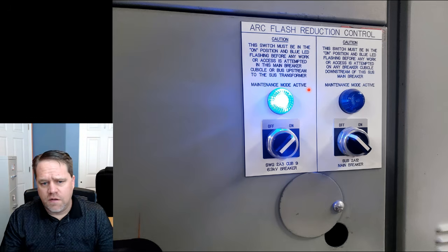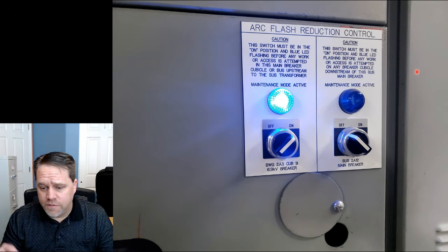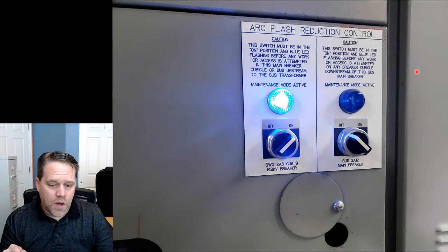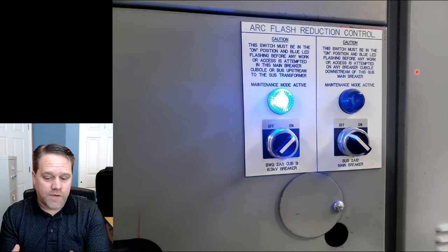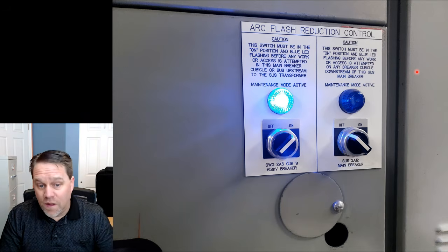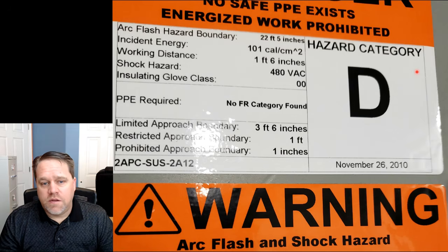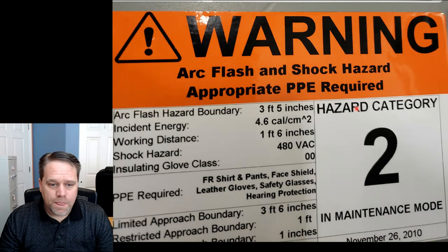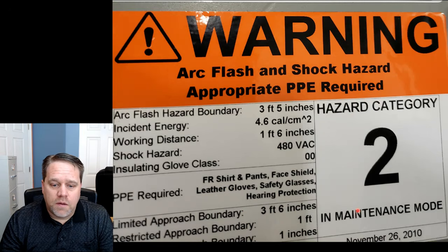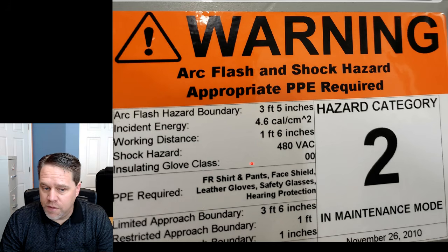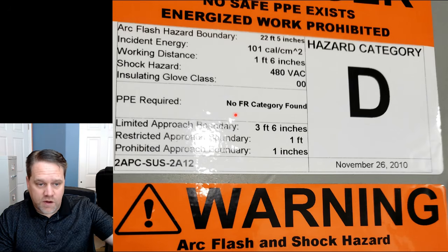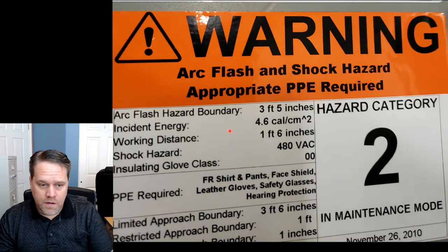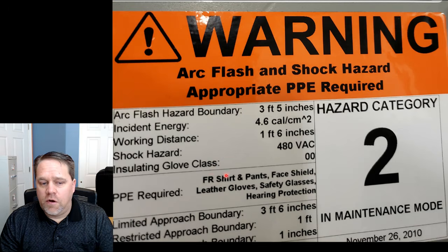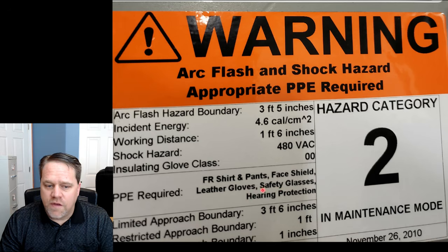What they have here is a relay, and then they also have optical fiber that actually is looking inside the equipment, and if they see a flash through the optical fiber line, it opens in less than one cycle. So it takes the danger from death, right, 101 calories. When I put it in maintenance mode, same piece of equipment, it goes all the way down to 4.6 calories, and you can see that's a significantly lower amount of PPE that's required. We went from instant death, there is no PPE, all the way down to fire retardant shirt, pants, face shield, gloves, safety glasses, hearing protection.